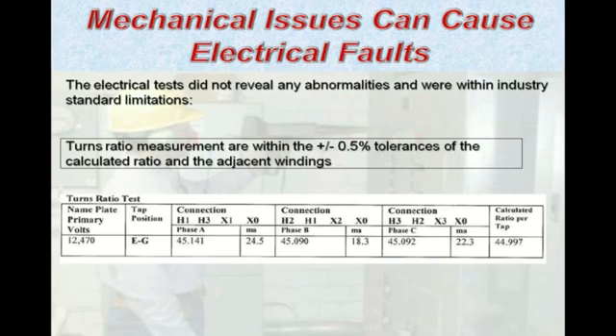The turns ratio has very tight tolerances, and as indicated here, the calculated ratio for these units, as well as the measurements of the adjacent coils, should not exceed 0.5% between each other or the calculated ratios. And these values here clearly indicate we're within specifications on both the high and the low side windings, so there's no turn-to-turn shorts at this point within the transformer.